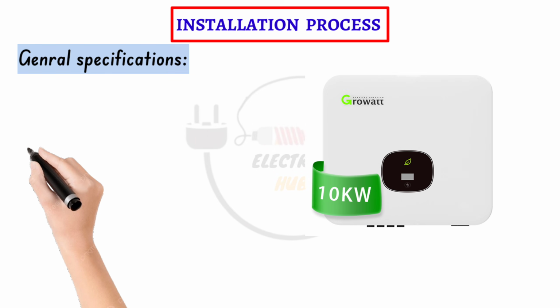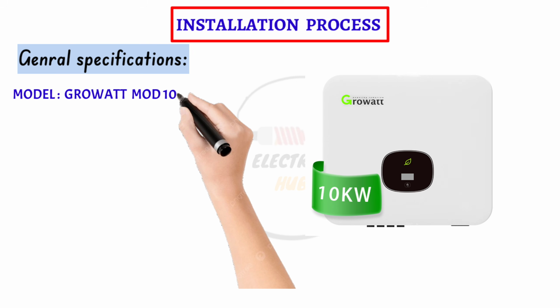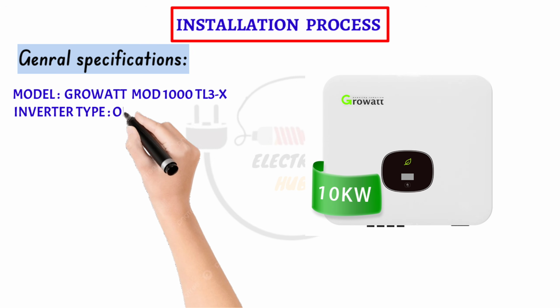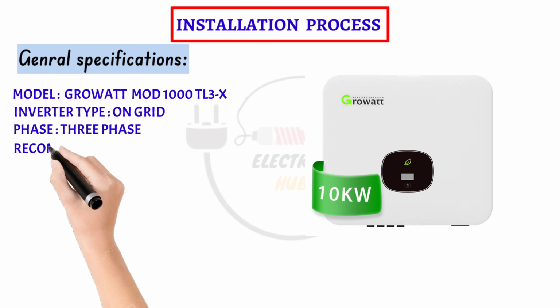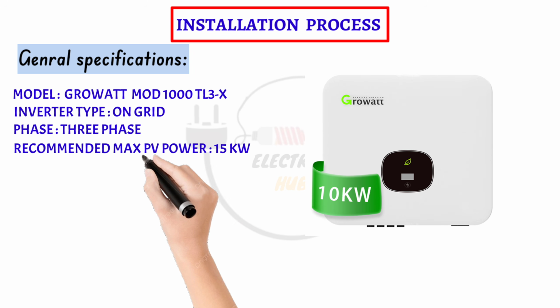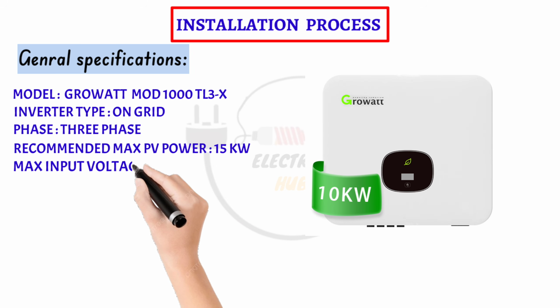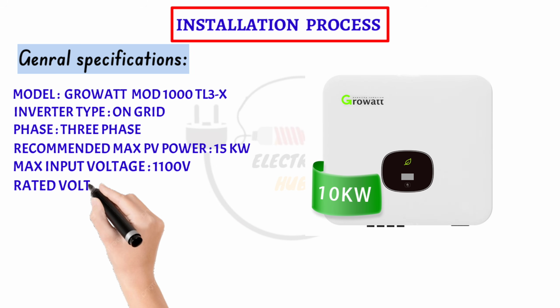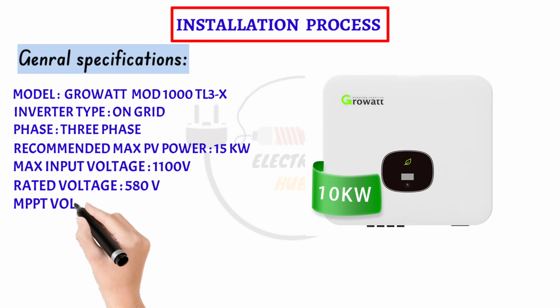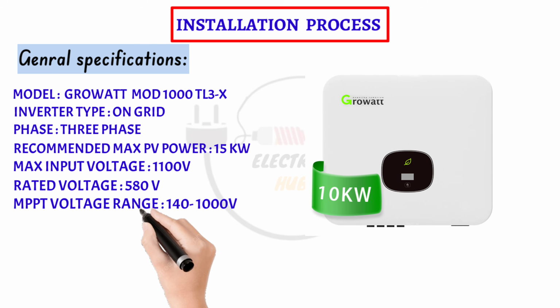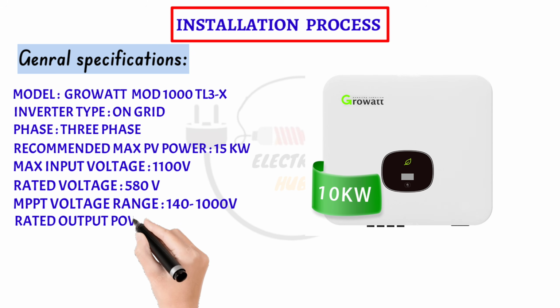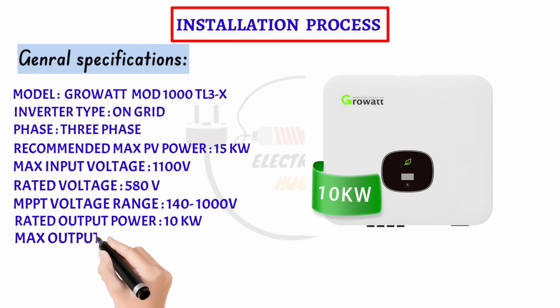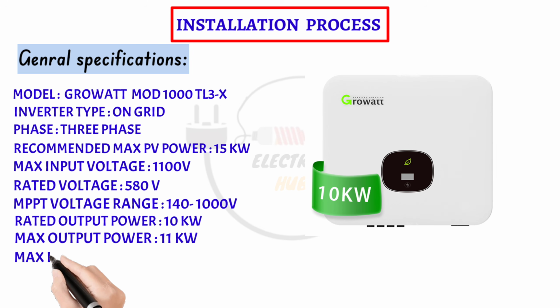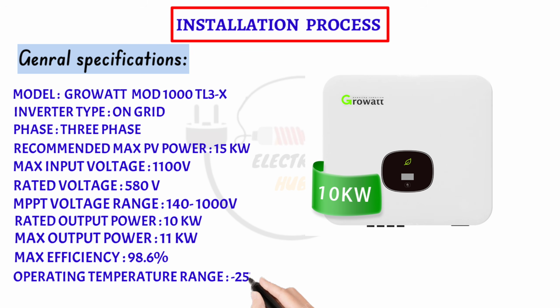General specifications. Model Growatt MOD 1000K TL3X. Inverter type on-grid. Phase 3 phase. Recommended max PV power 15 kW. Max input voltage 1100 volt. Rated voltage 580 volt. MPPT voltage range 140 to 1000 volt. Rated output power 10 kW. Max output power 11 kW. Max efficiency 98.6%. Operating temperature range minus 25 degrees Celsius to plus 60 degrees Celsius.